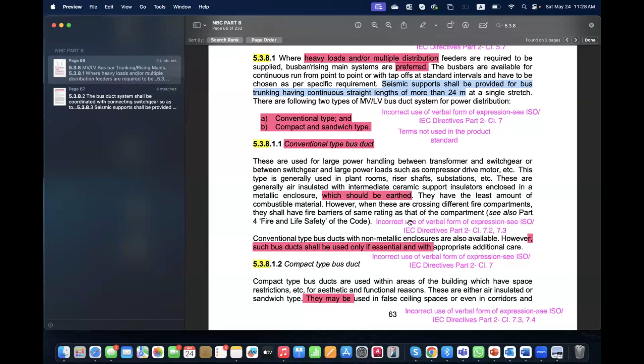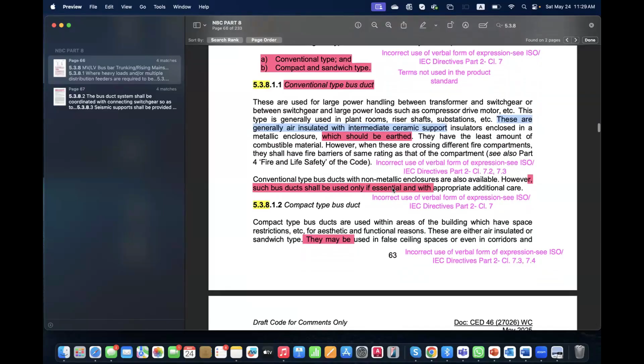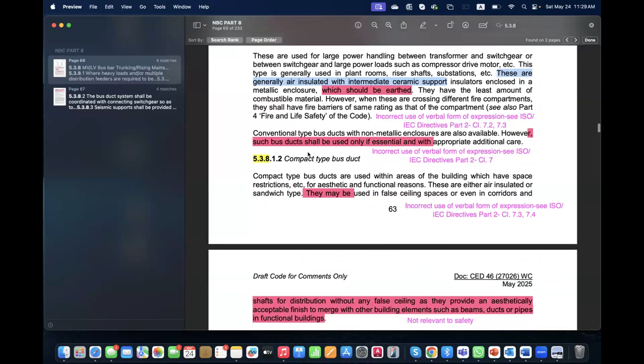"They have to have at least the least amount of combustible material" is once again a requirement for the product, not for the installation. "These are generally air insulated with intermediate ceramic support insulators enclosed in a metallic enclosure" is just information. It's not helping. It's not a requirement, recommendation, permission or possibility, none of this. "Such bus duct shall be used only if essential." What does this mean? Incorrect verbal form of expression and not objectively verifiable. "Compact type busbars may be used in false ceiling spaces or even in corridors." Once again, what are you trying to say? "In other cases, they should not be used" is again an incorrect verbal form of expression.